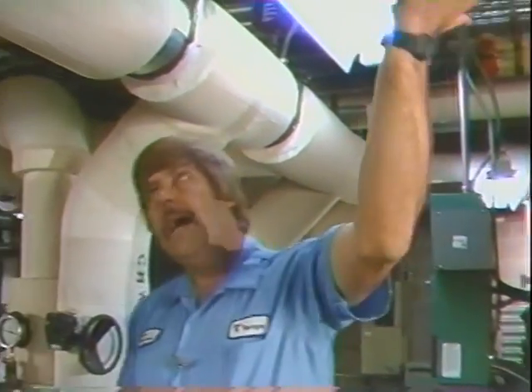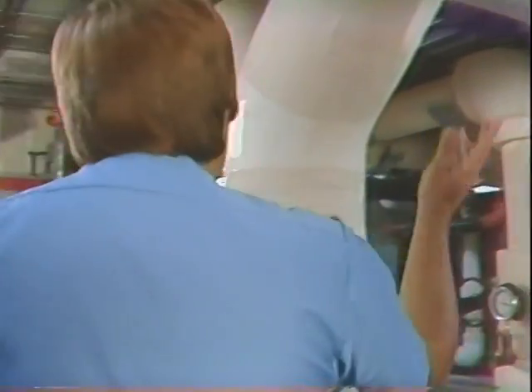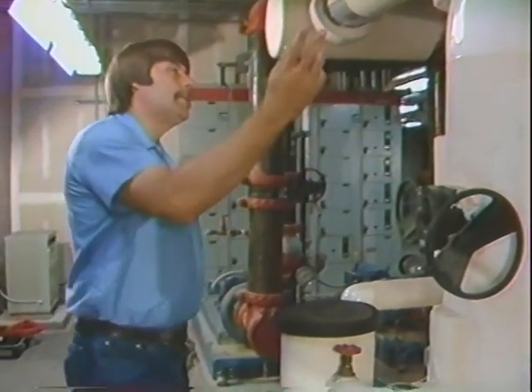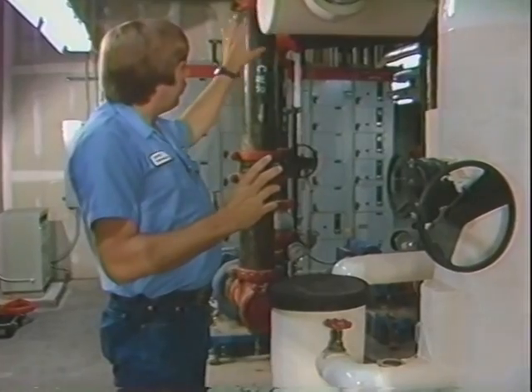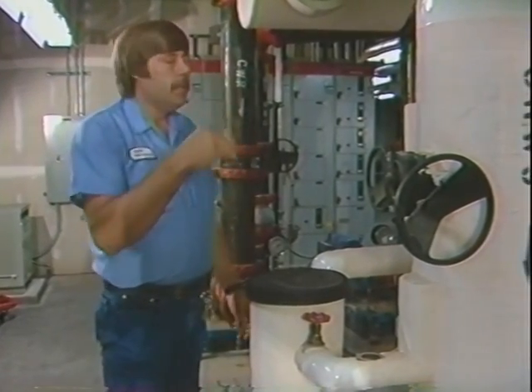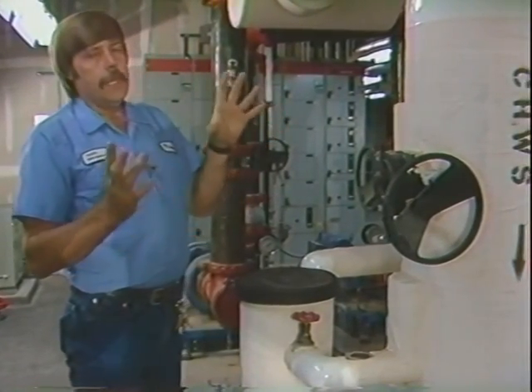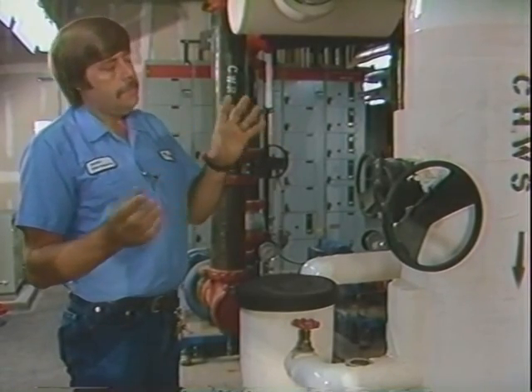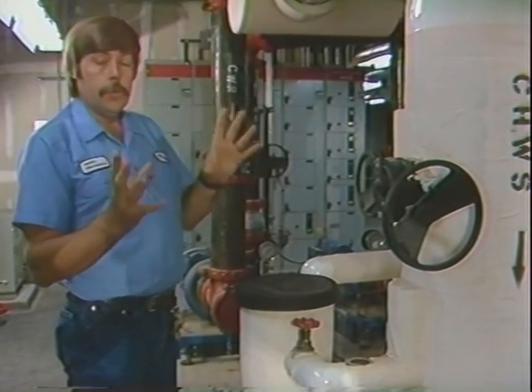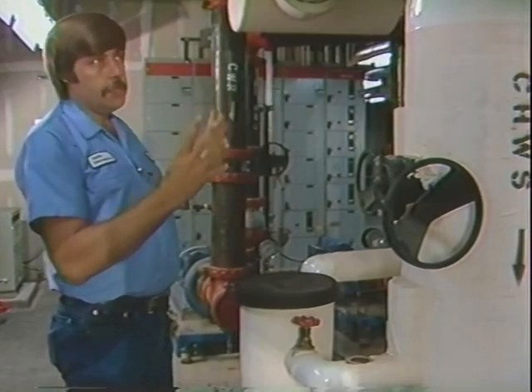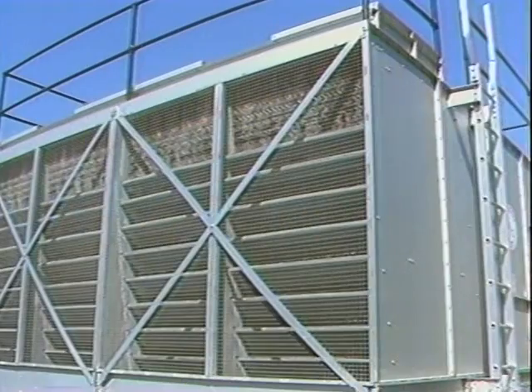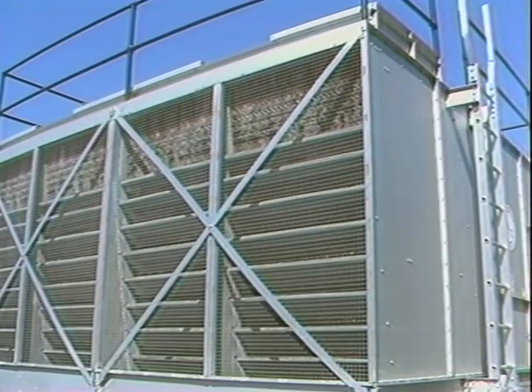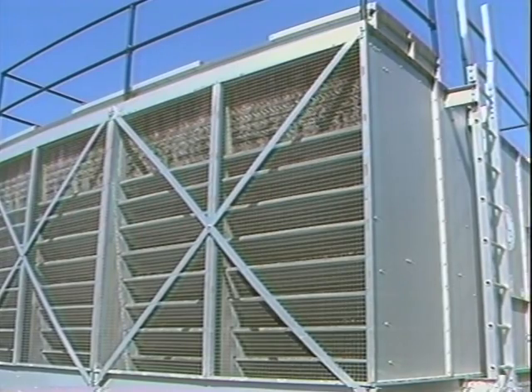It then comes through the lines, circulated through the pumps, and from this pumping station, it's pumped out to the different air handlers in the different buildings. In those air handlers, we take this chilled water. It is circulated through coils, which cools the air to condition the space in the different locations. A secondary loop of the water runs through a cooling tower on the outside of the building. Here, evaporation chills the water and is used in turn to cool the machinery inside, and another purpose.